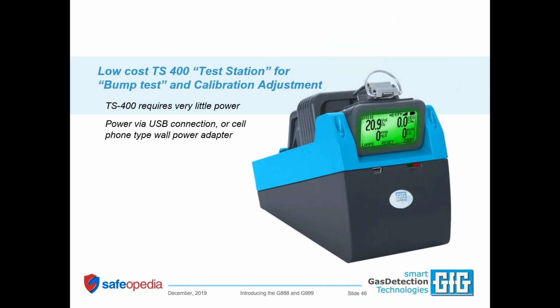We also have test stations that are about half the price of the full-size dock. The big difference is the docking station has an internal pump which pulls the gas from the cylinder. With the test station, you open the valve of the cylinder or push a trigger on the regulator to flow gas during the bump test. To do a full calibration, you put the instrument in calibration mode and then place it into the test station for adjustment.